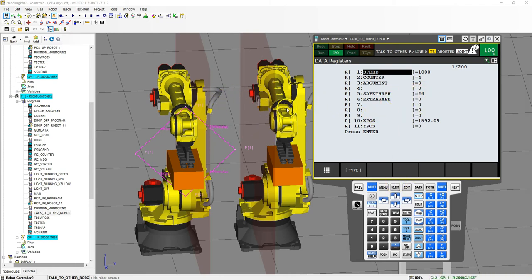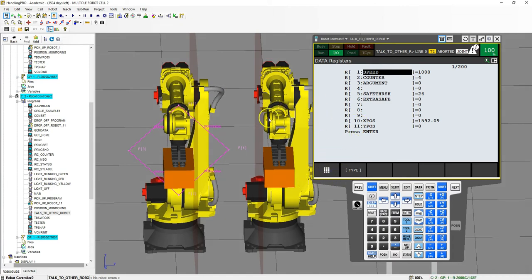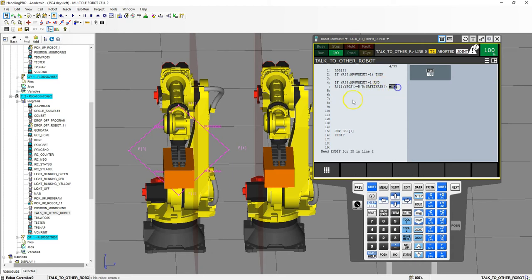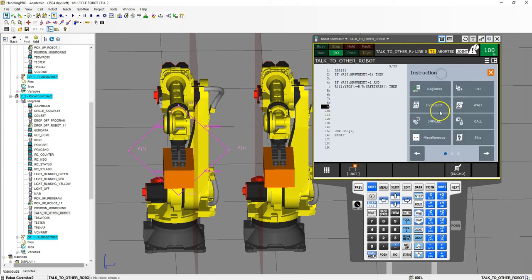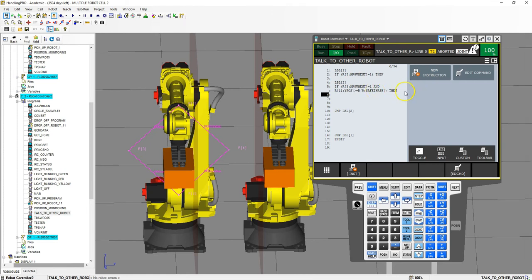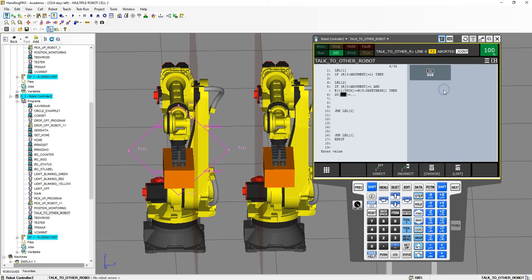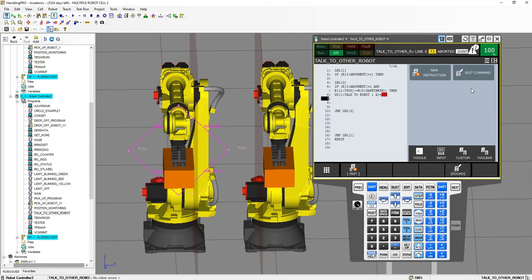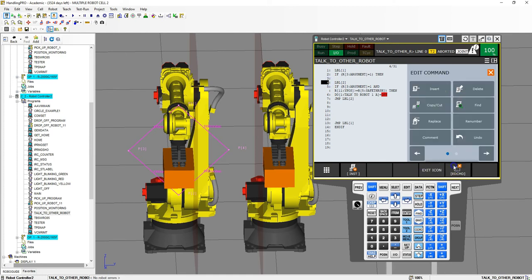So for robot controller two, we use greater than because everything is opposite. We add our then statement, insert a jump label at the bottom, and insert a jump label at the top. Now the lines of code are pretty simple — all we have to do is turn on a digital output stating we're in a safe position. So we go new instruction, IO, digital output, use number one which is 'talk to robot 1A', and we set this to off, meaning we are in a safe position. That's our first if statement, which is technically a while statement.